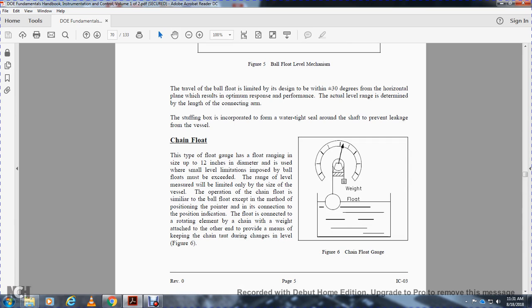Operation of the chain float is similar to the ball float, except in the method of positioning the pointer. The float is connected to the rotating element by a chain, with a weight attached to the other end, providing a means of keeping the chain taut during changes in level. Figure 6 shows the chain float level, the float, and the weight.